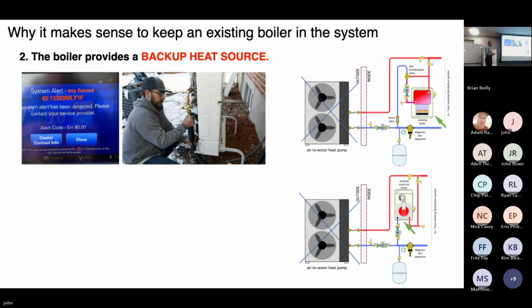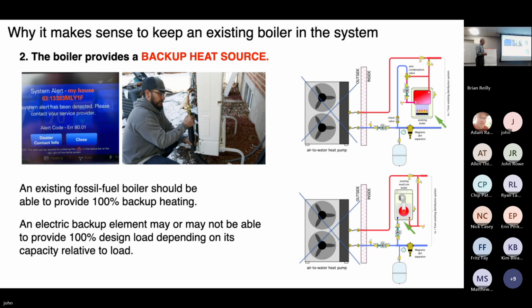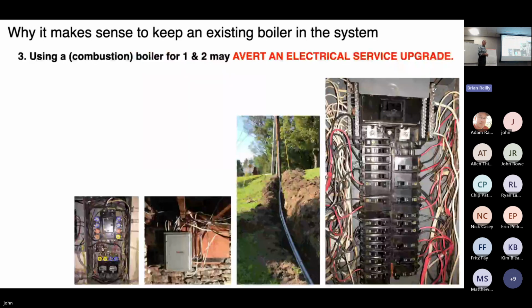Okay. So having both supplemental and backup is justification for a boiler in there. Electric backup may or may not be able to provide 100%. It depends on the capacity relative to the load. You know, do you have 3 kW of backup heat? Do you have 12 kW of backup heat? Yes, you can get electric boilers that will provide 100%, but make sure that the service entrance is up to handling that. And that's the next slide.